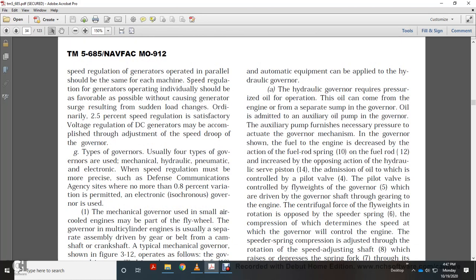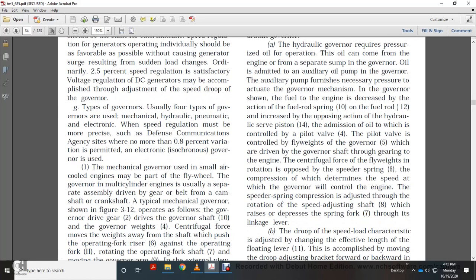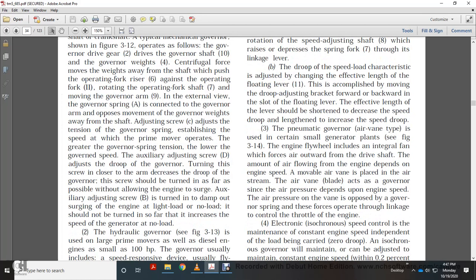The hydraulic governor can be made to operate accurately, smoothly, and with remote control. All automatic equipment can be applied to the hydraulic governor. It requires pressurized oil, which can come from the engine or from a separate governor sump. An auxiliary pump furnishes the necessary pressure to actuate the governor mechanism. Fuel to the engine is decreased by the action of the fuel rod spring; fuel is increased by the opposing hydraulic action, controlled by the pilot valve. The pilot valve is controlled by the flyweights, which are driven through gearing to the engine. Centrifugal force of the flyweights is opposed by the speed spring; spring compression determines the speed at which the governor controls the engine. Speed droop load characteristics are adjusted by changing the effective length of the floating lever.